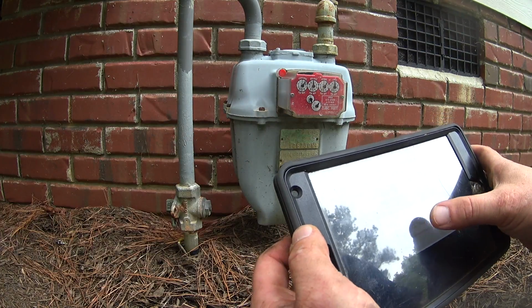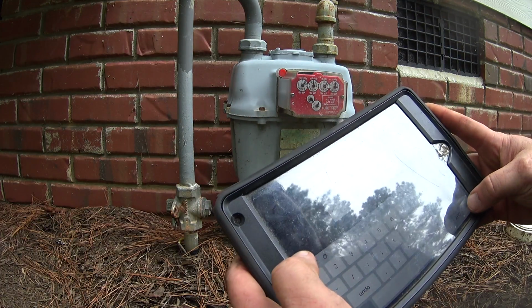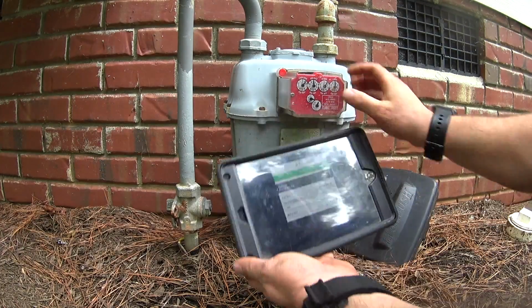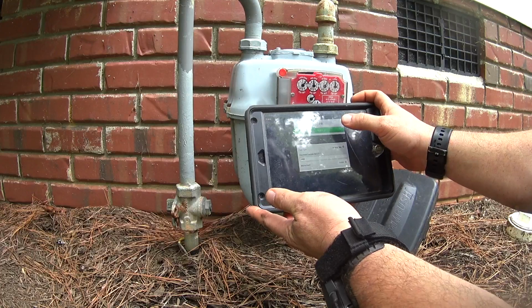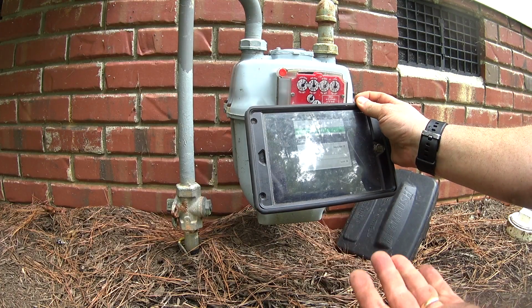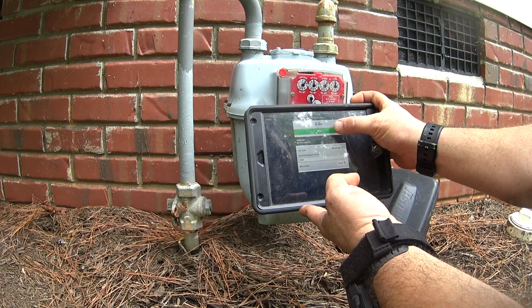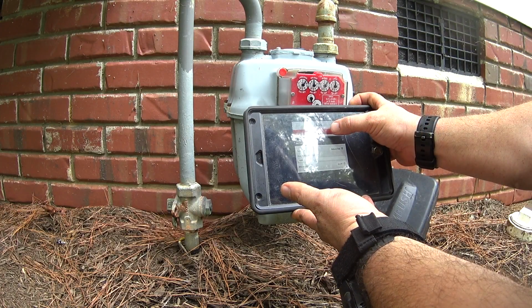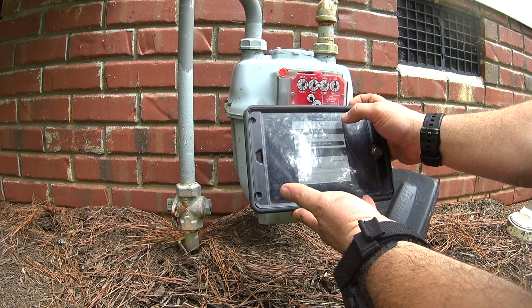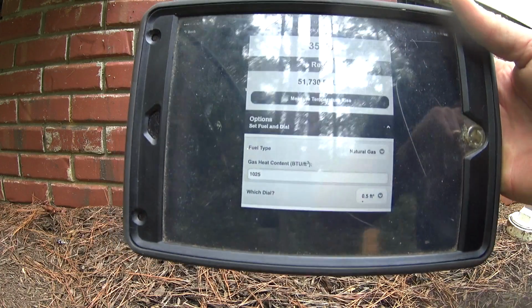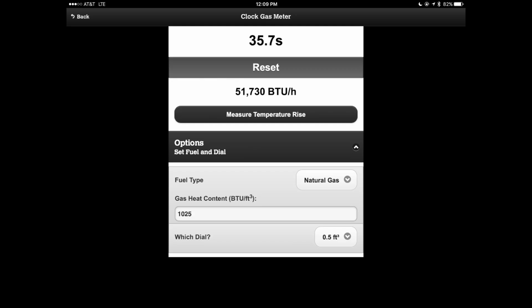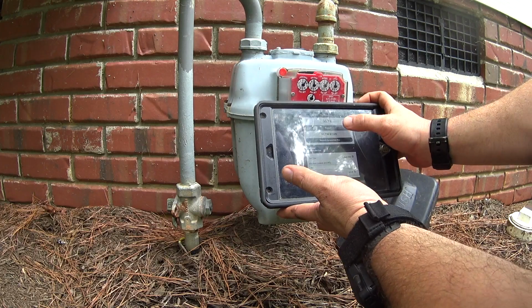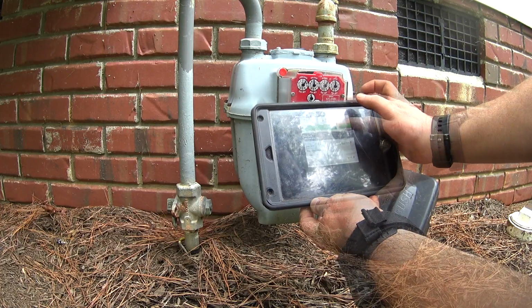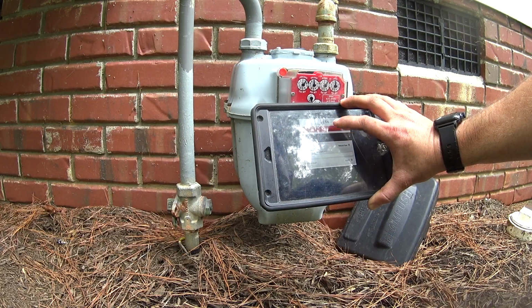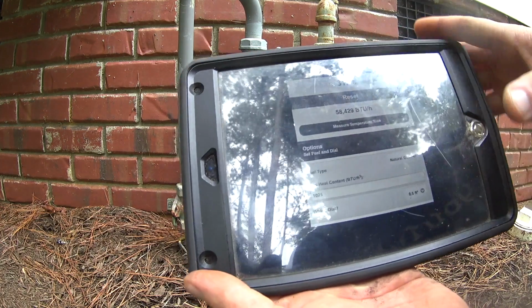We're gonna clock the gas meter, gas heat content of 1025, start on the half-foot dial, and start it when the dial hits the bottom, and stop. So a 60,000 BTU unit is showing 51,730. We're gonna do it one more time when the meter hits the bottom again, and start and stop. 58,429.